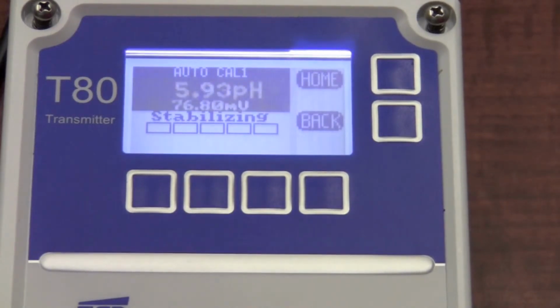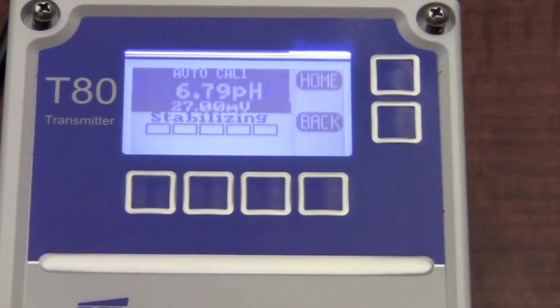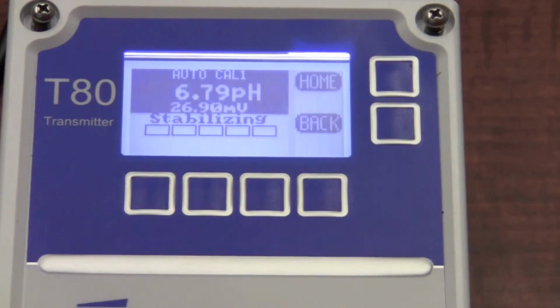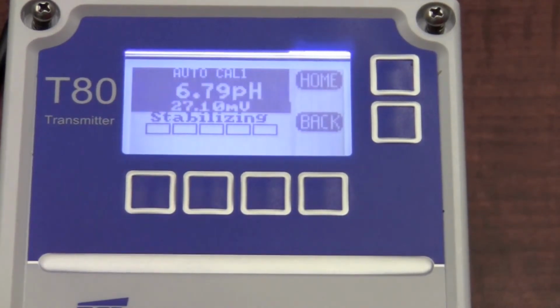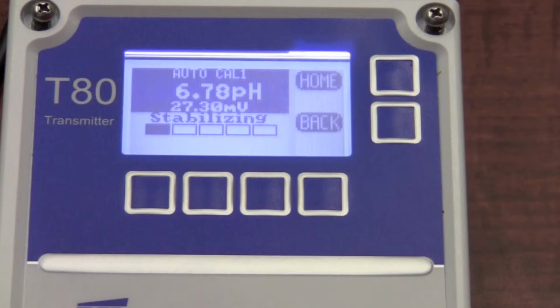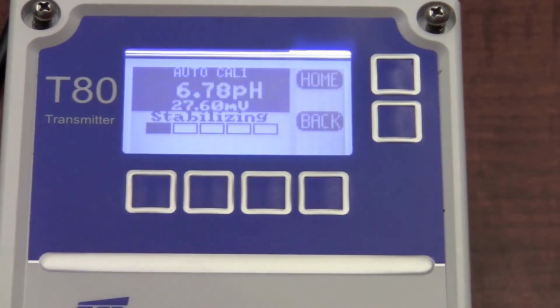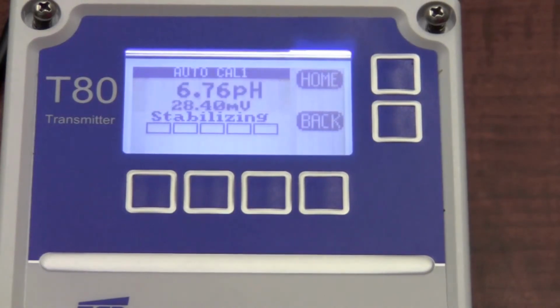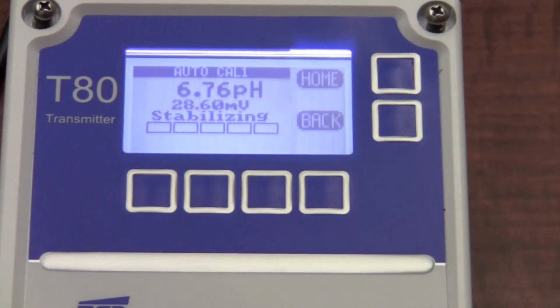I'm placing that in 7 buffer. As you can see, the T80 starts to interrogate the transmitter, reading the millivolt value coming off of the pH electrode. It's going to wait for stabilization, and once it's satisfied that it is stable, the T80 thinks it's as close to one of the standard calibration solutions of 7.